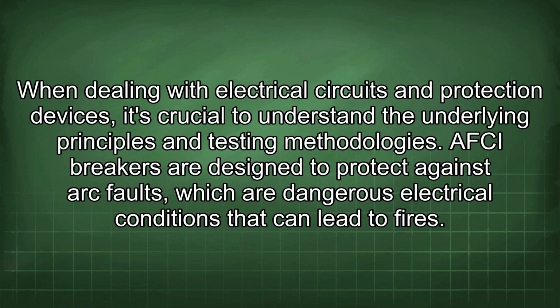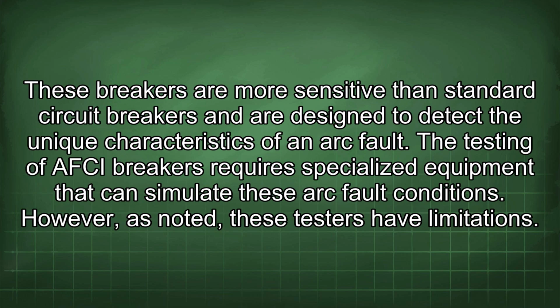When dealing with electrical circuits and protection devices, it's crucial to understand the underlying principles and testing methodologies. AFCI breakers are designed to protect against arc faults, which are dangerous electrical conditions that can lead to fires. These breakers are more sensitive than standard circuit breakers and are designed to detect the unique characteristics of an arc fault. The testing of AFCI breakers requires specialized equipment that can simulate these arc fault conditions.